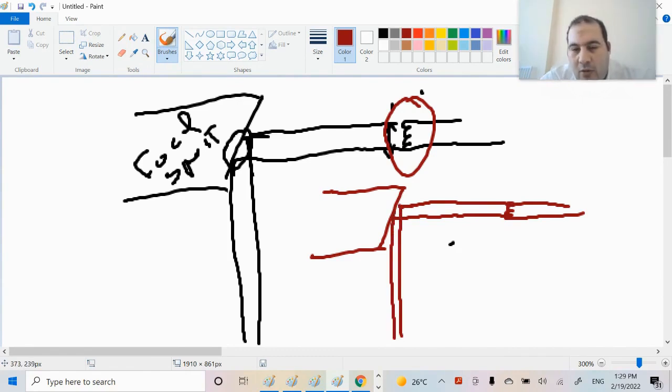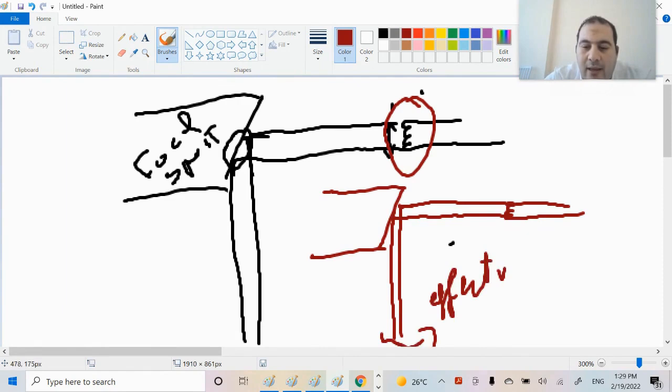What they call the actual focal spot size is specifically the location where bombarding takes place between the electrons and the anode. The effective focal spot is the projection of the area of the actual focal spot from the anode onto my image receptor, which we refer to as the effective focal spot.